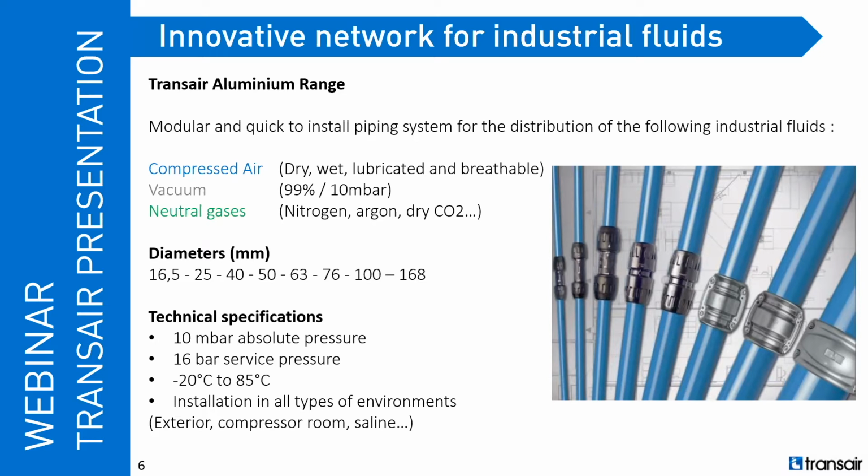Our range of service pressure is from 10 millibars absolute pressure to 16 bars. Our range of temperature is from minus 20 degrees Celsius up to 85 degrees Celsius. And the system can be installed in any type of environment: exterior, compressor room, saline, etc.